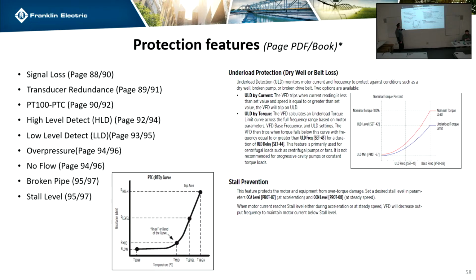Broken pipe's not applicable to you guys. Basically, if the drive is running at full speed and the pressure just never comes up, it'll say that you have a broken pipe most likely, and start looking at the system. And then stall level is basically this. It's tied into the high level detect, and it's just asking like what your amperage is. Oh, here's the underload stuff. This is the dry well versus belt loss I was talking about at the beginning. That's the underload.